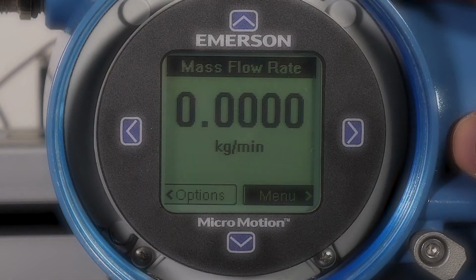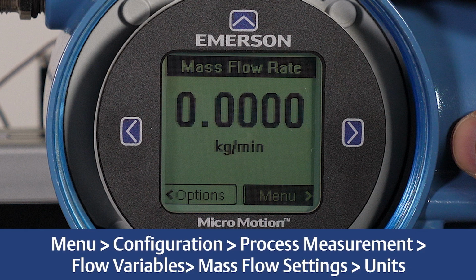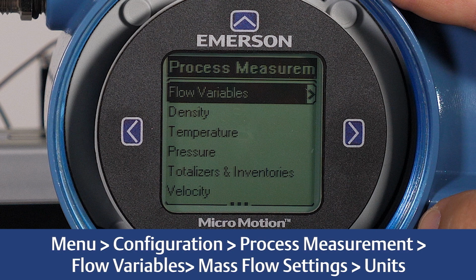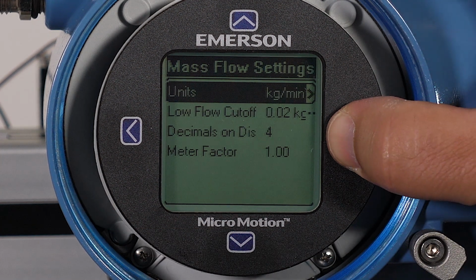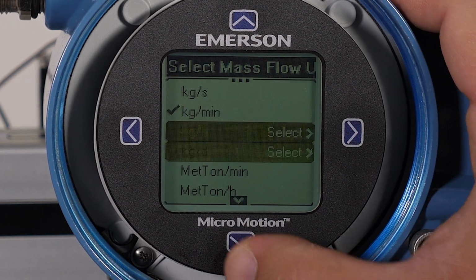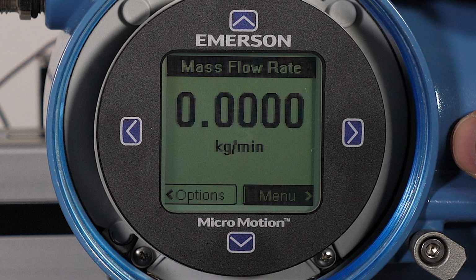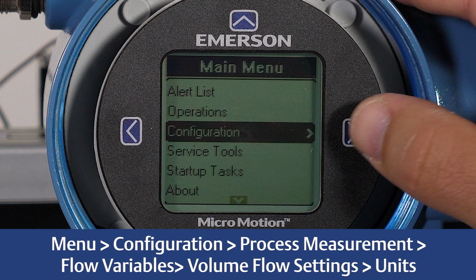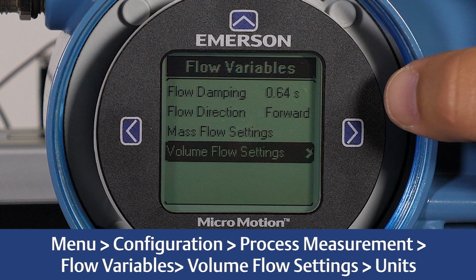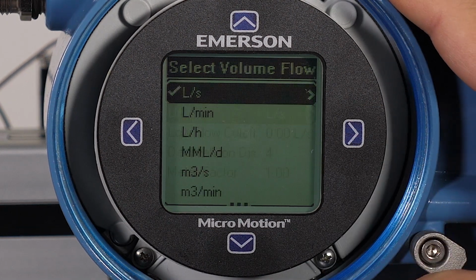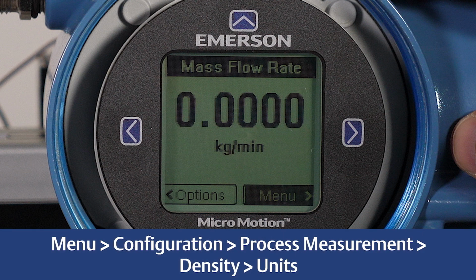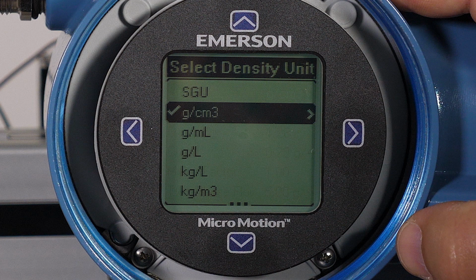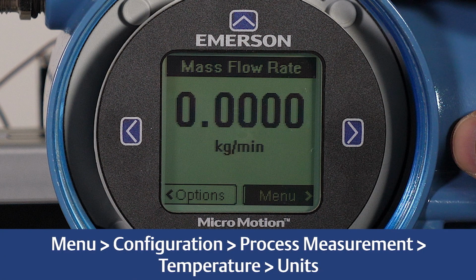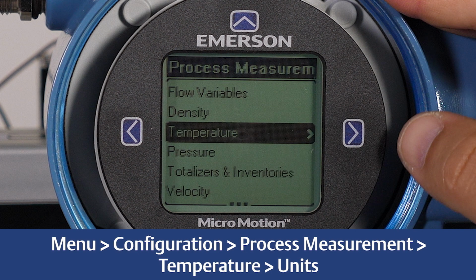Configure the units for mass flow, volume flow, density, and temperature using the following procedures. For configuring mass flow units, use the display by selecting Menu, Configuration, Process Measurement, Flow Variables, Mass Flow Settings, Units. For configuring volume flow units, use the display by selecting Menu, Configuration, Process Measurement, Flow Variables, Volume Flow Settings, Units. For configuring density units, use the display by selecting Menu, Configuration, Process Measurement, Density, Units. For configuring temperature units, use the display by selecting Menu, Configuration, Process Measurement, Temperature, Units.